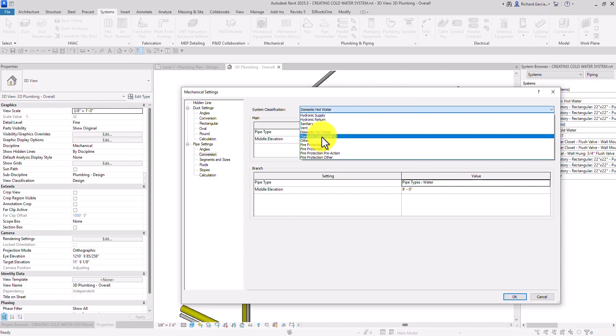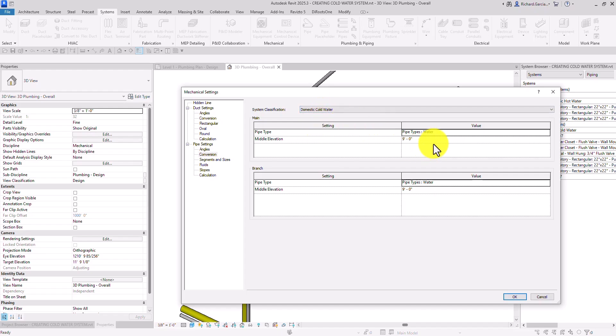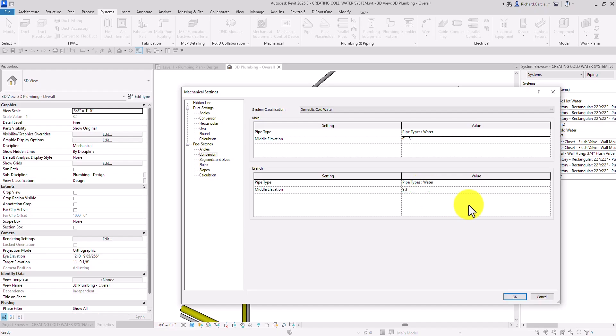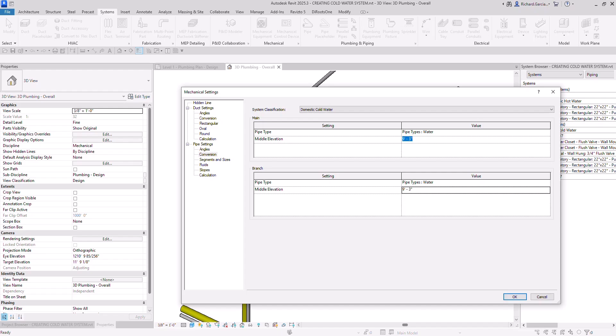Now go to Domestic Cold Water in the settings. Make sure the pipe type is Water, and I'll change the middle elevation or offset to 9 feet 3 inches — type '9 space 3' for 9'-3". I'm doing this to minimize opportunities for piping interference. I changed the offset for hot water and cold water so the automatic pipe layout for cold and hot water pipes are not on the same elevation, since there's a possibility those two pipes will interfere or clash.